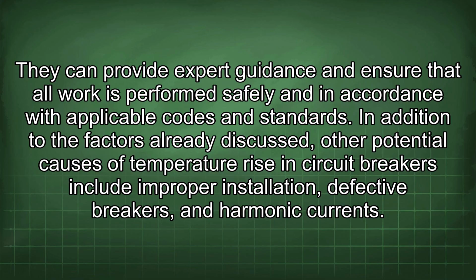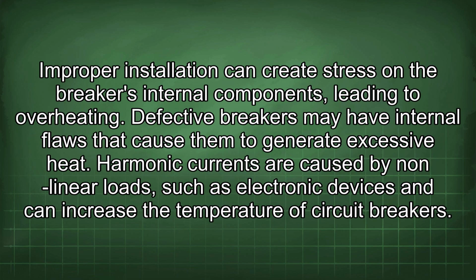In addition to the factors already discussed, other potential causes of temperature rise in circuit breakers include improper installation, defective breakers, and harmonic currents. Improper installation can create stress on the breaker's internal components, leading to overheating. Defective breakers may have internal flaws that cause them to generate excessive heat. Harmonic currents are caused by nonlinear loads, such as electronic devices, and can increase the temperature of circuit breakers.